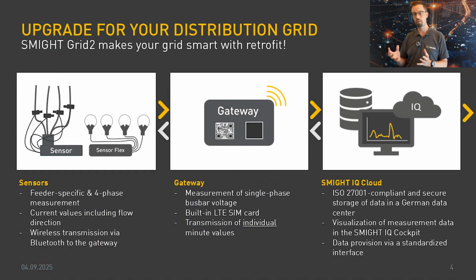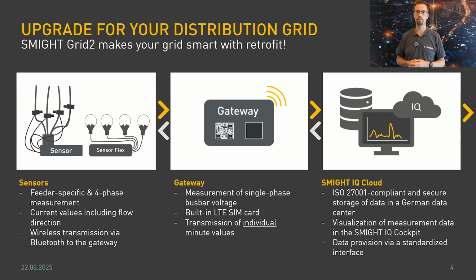The starting point for our product range has always been feeder level monitoring. We have sensors which we usually connect to the low voltage feeders, whether in a secondary substation or distribution cabinet, connecting onto the three power phases but also the neutral line. From those sensors we capture current information: the current magnitude, flow direction, and phase angle. That data is transmitted via Bluetooth up into our gateway, which then takes a single phase voltage measurement. That's quite important for today's talk because we're talking about three-phase monitoring.